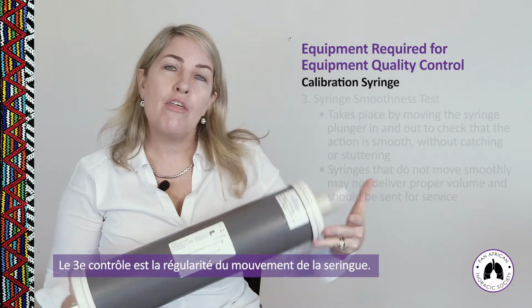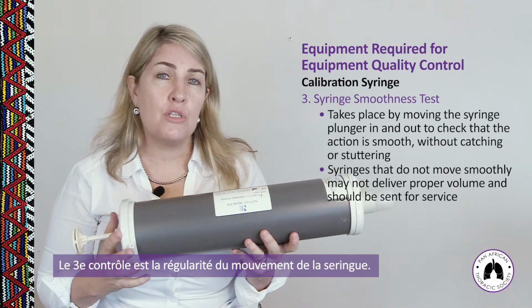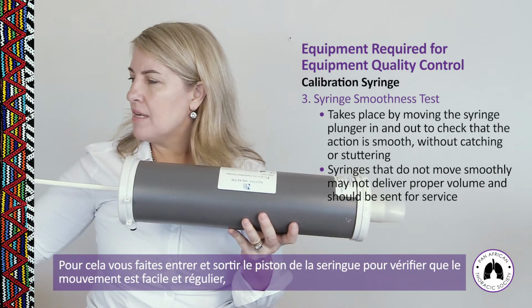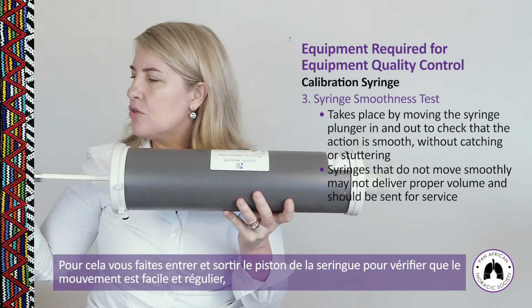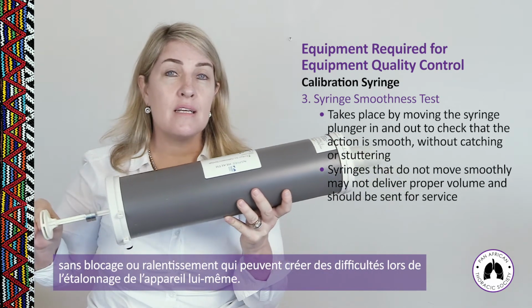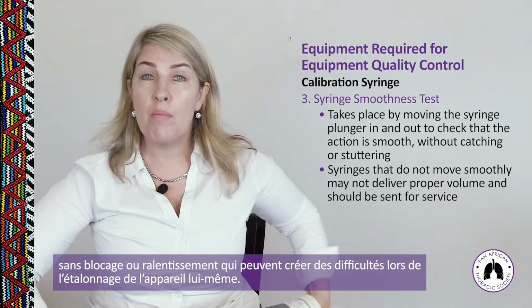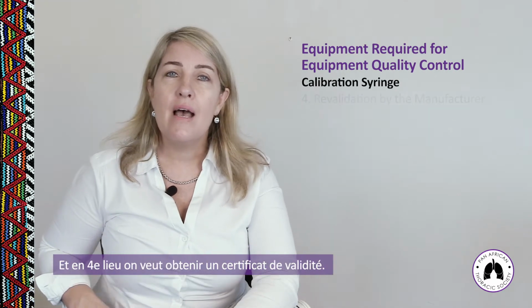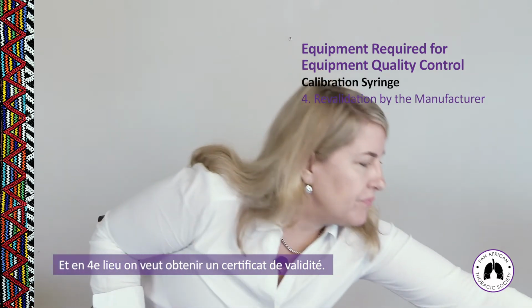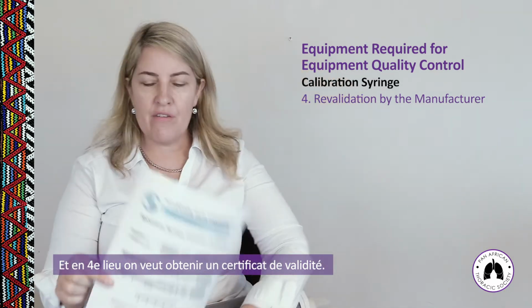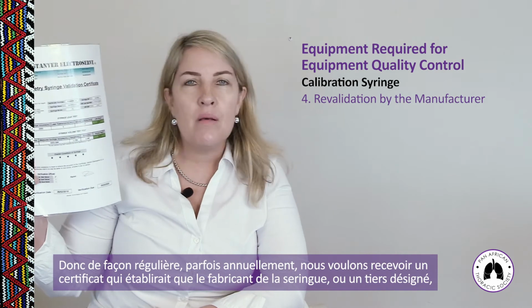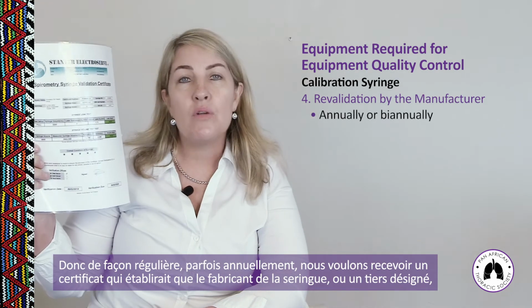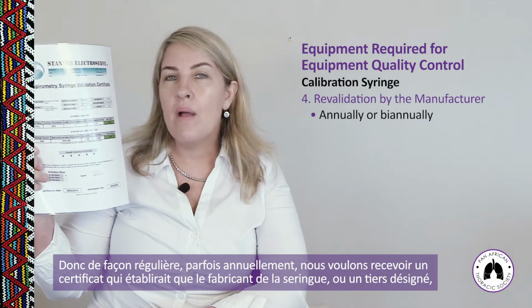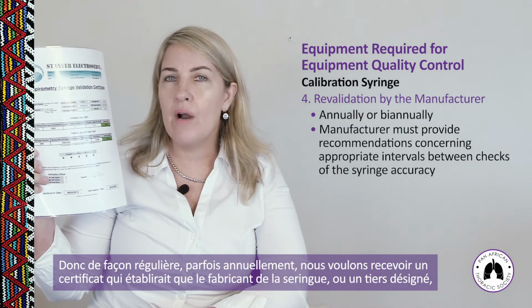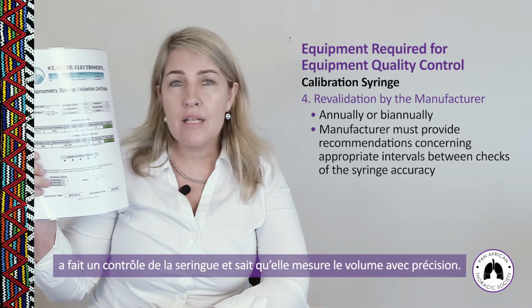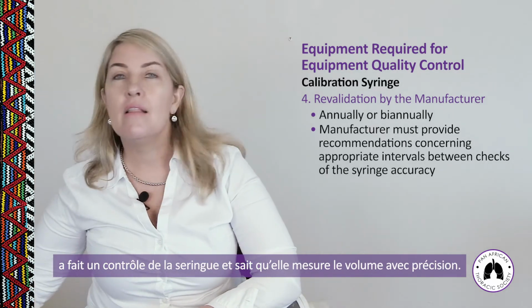there's a leak. Third thing is that you want to do a syringe smoothness check. So that is just moving the plunger in and out of the syringe to make sure that it is moving freely, that there's no stickiness. That's going to result in problems when you're calibrating the machine itself. And lastly, we would be looking for a calibration verification check. So on a regular basis, sometimes annually, we would want to be getting a certificate whereby the manufacturer of the syringe or a designated party has checked the syringe and knows that it is reading the volume accurately.